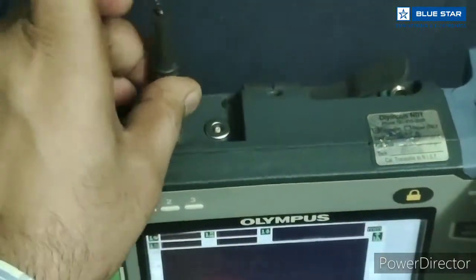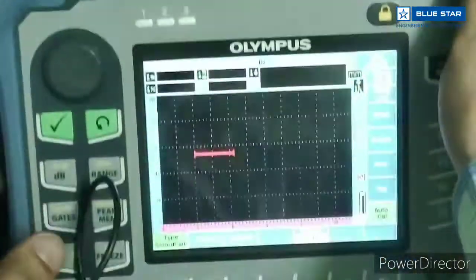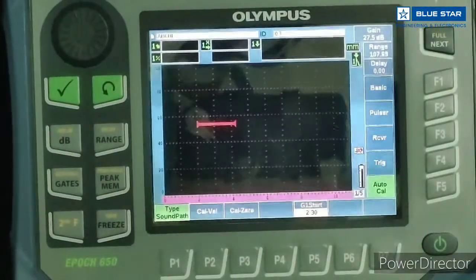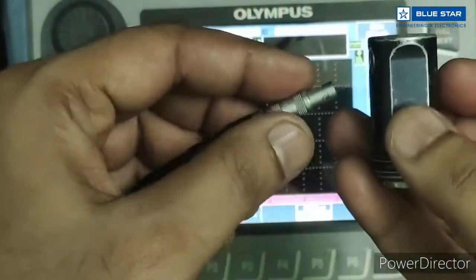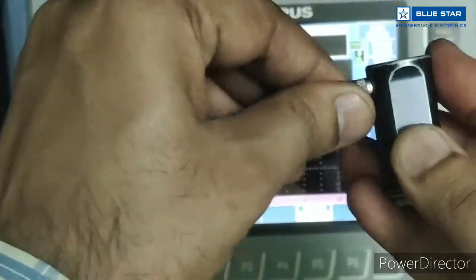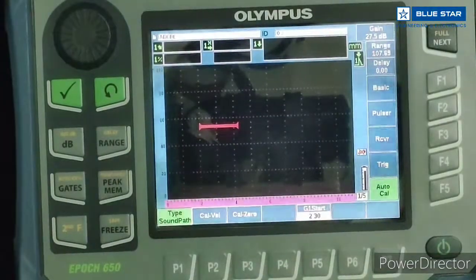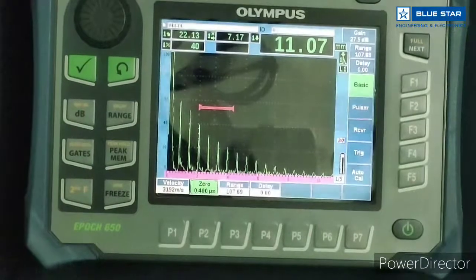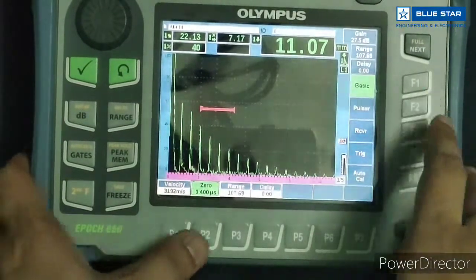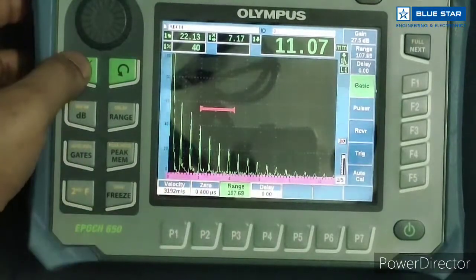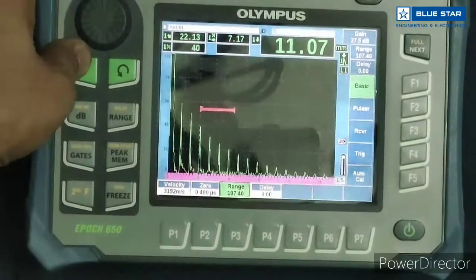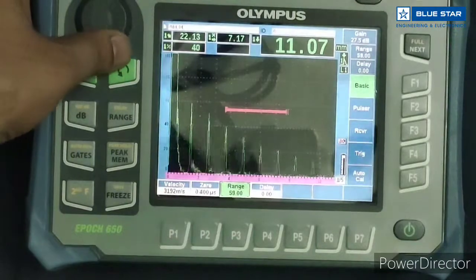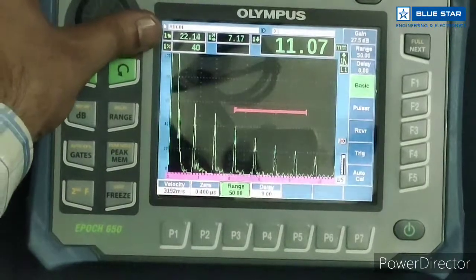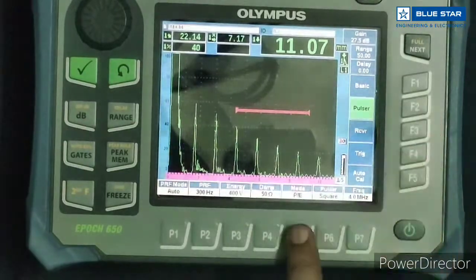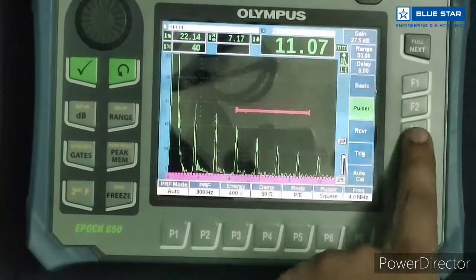Calibration setting of single crystal transducer. We are calibrating single crystal transducer on V2 block. First select range, approximate 50 mm. Now press F2 and go to pulser mode PE square and 4 MHz.